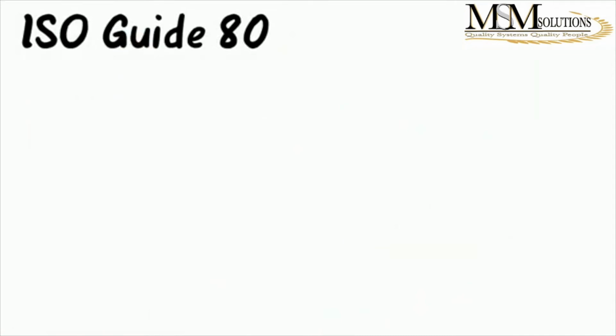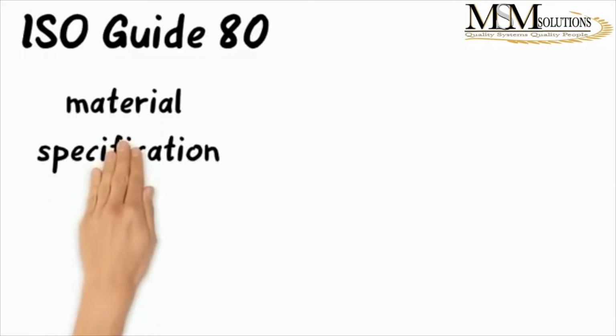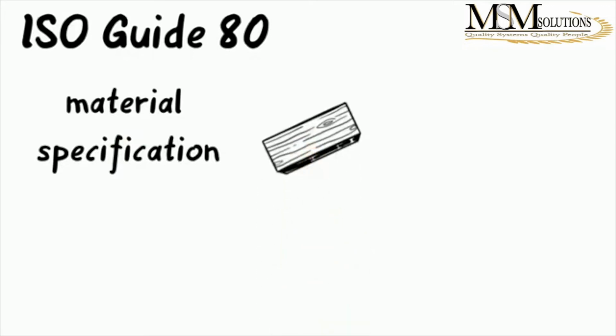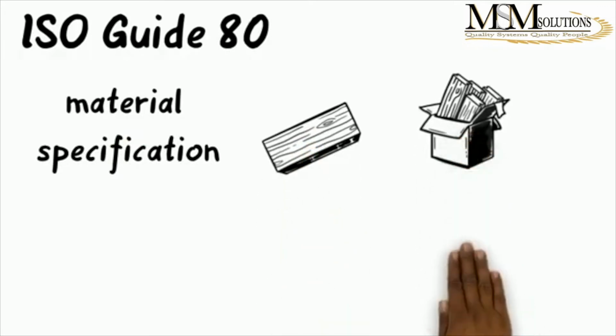The ISO Guide 80 gives you guidance in how to prepare in-house quality control material. In this guide, it will talk about aspects of material specification. How do you choose the material you're going to use? Where do you source it? Material sourcing. Material processing, meaning your primary preparation, your drying, your milling, pulverization, or whatever material processing is required.